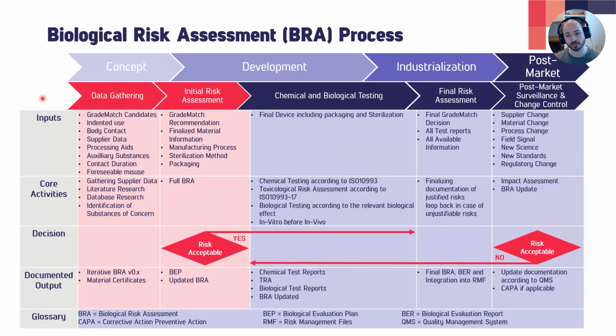And for biocompatibility, what you would do in the beginning is you would start with gathering data. Then you would do an initial risk assessment. Then you would do a chemical and biological testing phase. And then you have a final risk assessment. And then you would launch the device. And then you have a post-market surveillance phase and change management. So either the market gives you data, or you will have to change the device and reassess its safety.